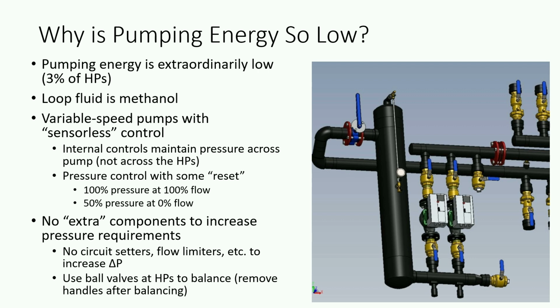So why is the pumping energy so low? Like I said, 3% of what the heat pumps use. One thing that helped is that methanol is the fluid, and methanol is pretty well known to be the fluid with the lowest pumping power, so that helped. There were variable speed pumps. I like to call this sensorless control, because in a traditional geothermal building, you have a two-way valve on every heat pump. So when the heat pump runs, the valve opens, and when the heat pump turns off, it closes.